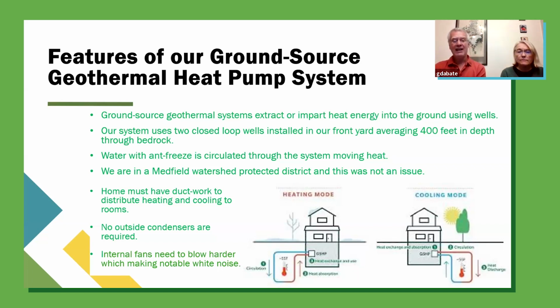But what isn't silent is that heat pumps don't heat the air up as much as a natural gas system, so they have to blow more air, which means you need stronger fans. So it is a little louder inside the house—like a white noise background from the fan when it's running, definitely louder than with our conventional HVAC.